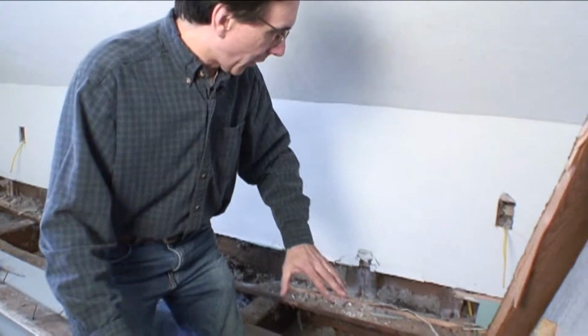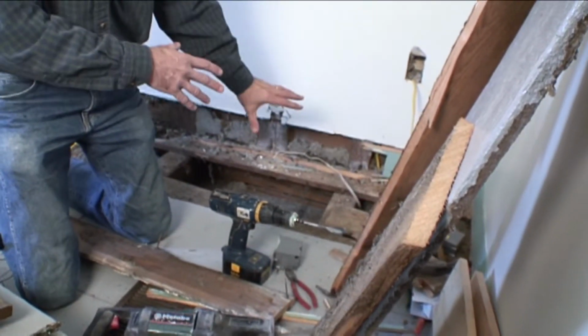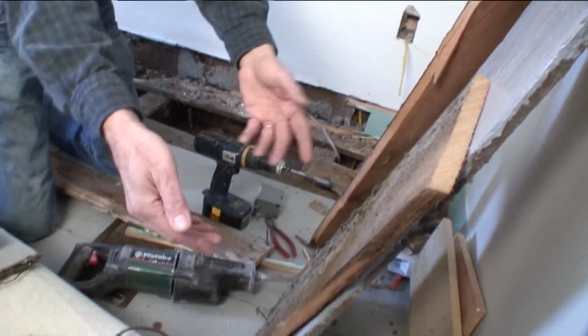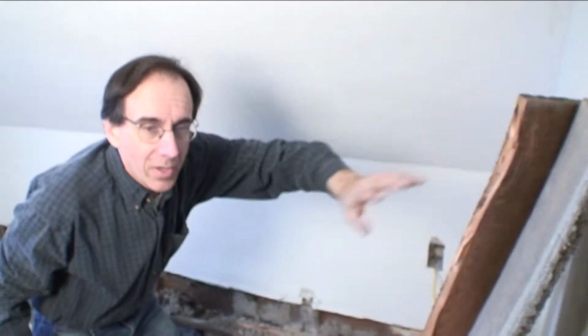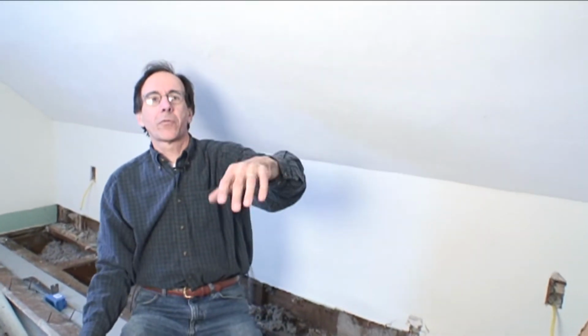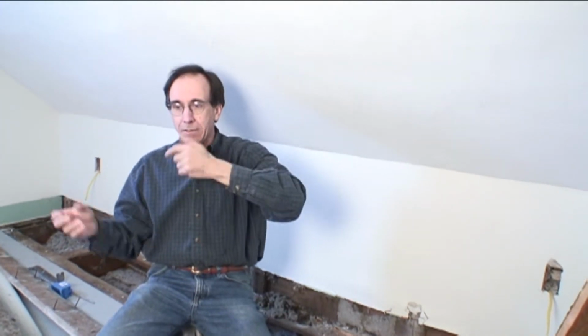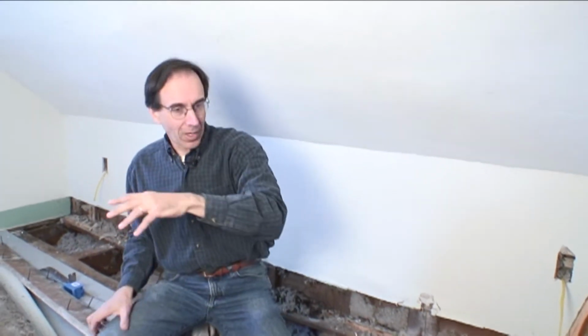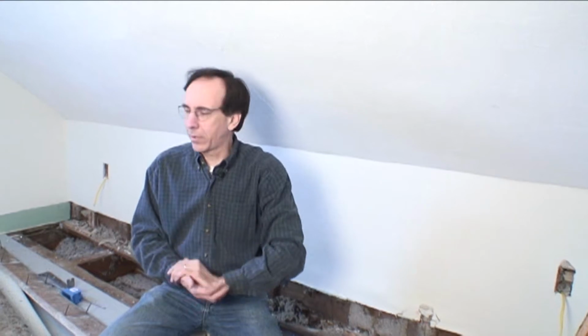So what we're going to do is, I'm pretty much done here now, close this up again, come over here, lift some boards, get a wire run up into this wall with an outlet here, a wall switch here, and a wall fixture a little higher up. That gives us lighting for when you walk into the room — just flip the switch and go about your business. You can have additional lighting on a table or with a floor lamp or whatever.